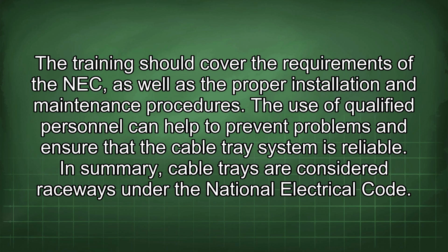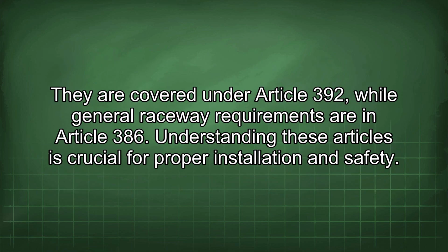In summary, cable trays are considered raceways under the National Electrical Code. They are covered under Article 392, while general raceway requirements are in Article 386. Understanding these articles is crucial for proper installation and safety.